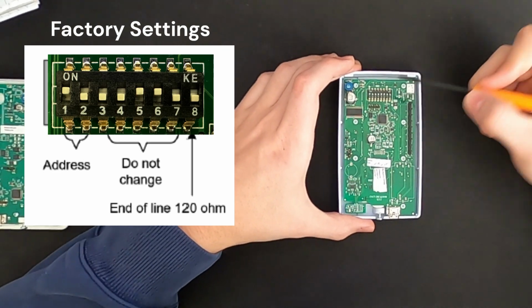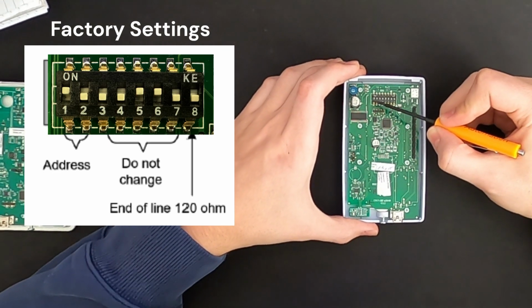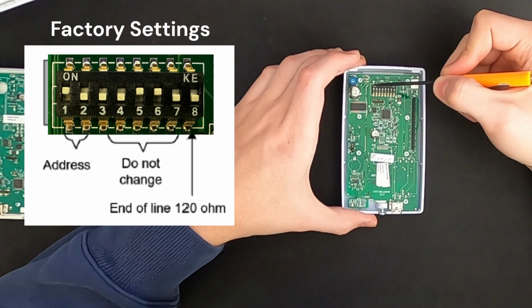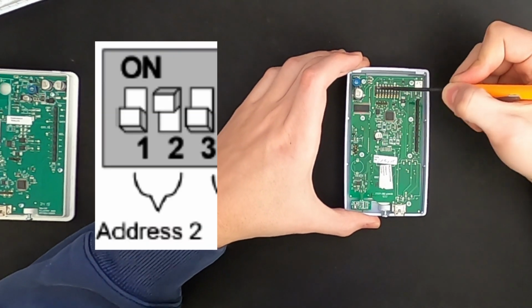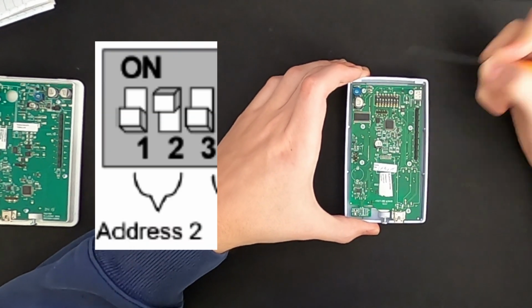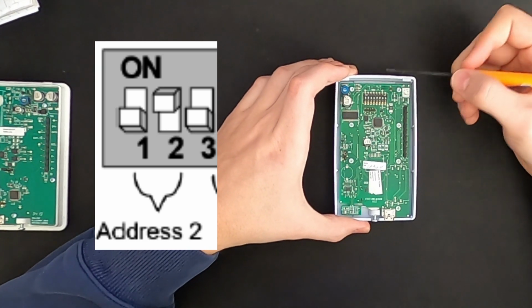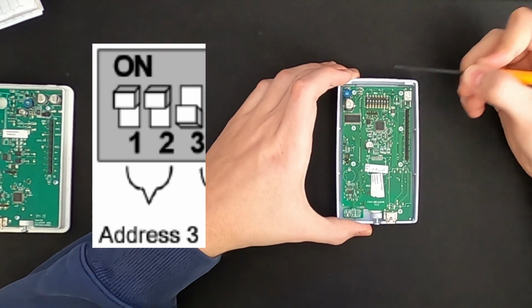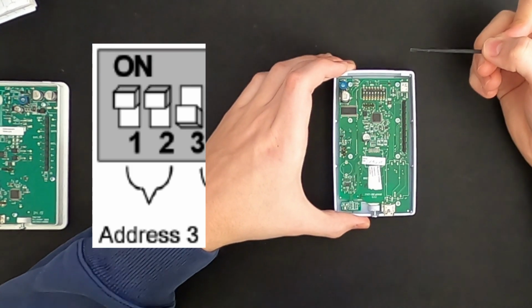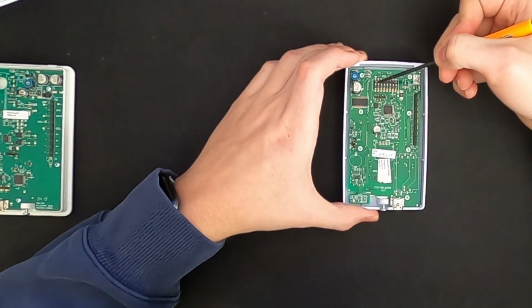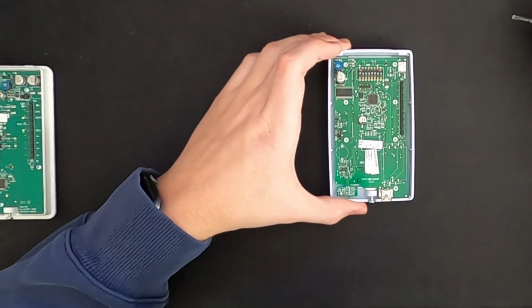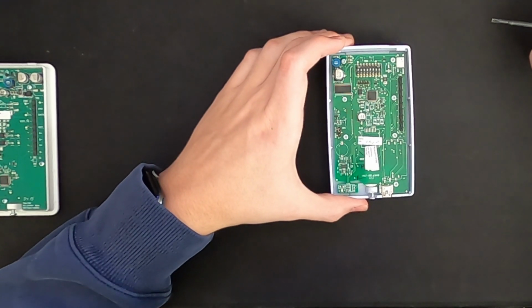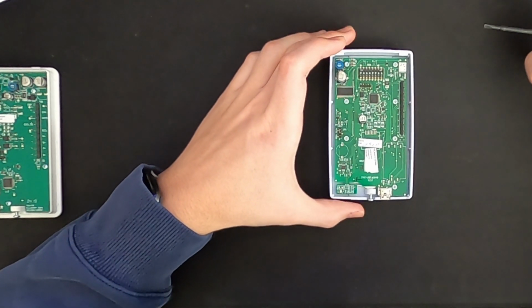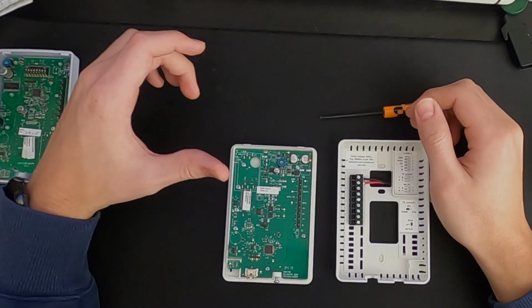To set your address to 1, you'll have this first dip switch up. For 2, you'll have the first one back down and the second one up. And to set it to 3, you'll have 1 and 2 both up, like so. I'll switch this back to 1 since it's 1 on my network, and you should be good to go.